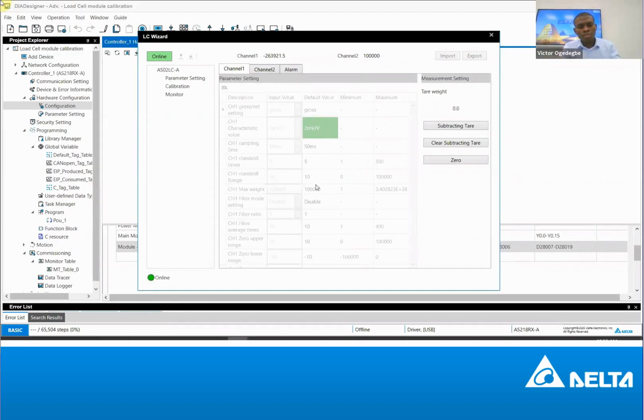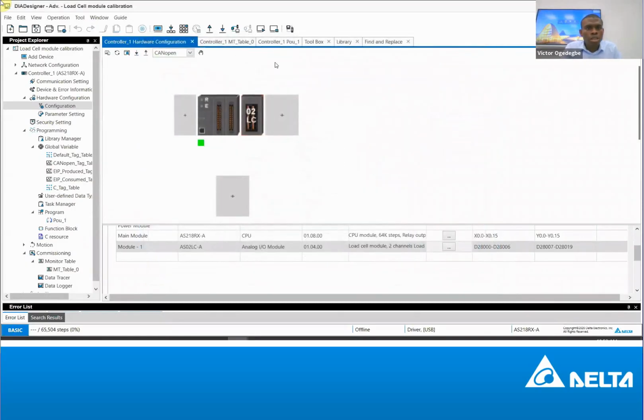So now let's go back to our presentation. Basically, this is where you set up the basic setup of the load cell module, and then you are ready to program your machine. Then the digital value you have, you can tell your machine, if I read 1000, do this. If I read 2000, execute this command. It's just as simple as other PLC programs or algorithms that you implement. Then I close the load cell module.